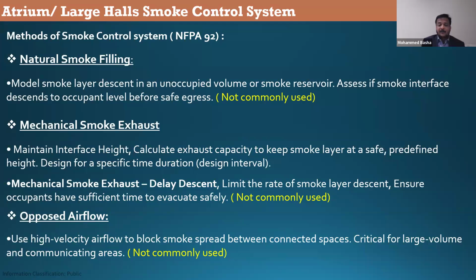If the time for occupant evacuation is less than the smoke filling time, then you do not need a dedicated smoke control system in the building. This is called natural smoke filling. Basically, we are filling the smoke as a reservoir at the top of the building. This will not be applicable in the atrium because you will have communicating spaces in the atrium.